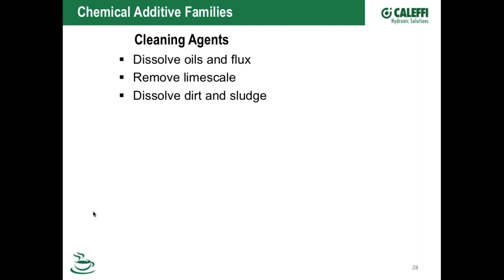We need to get all that stuff out, and it sometimes takes more than just putting water in and flushing, because to break those oils and assembly lubes that might be in your boilers, you kind of need a detergent or soap or cleaner. So I'm of the opinion you want to fill up your system, pressure test it. If you don't have a leak, fill it with the water on the job site and put a cleaner in there, a detergent. You can buy those cleaners from hydronic suppliers.